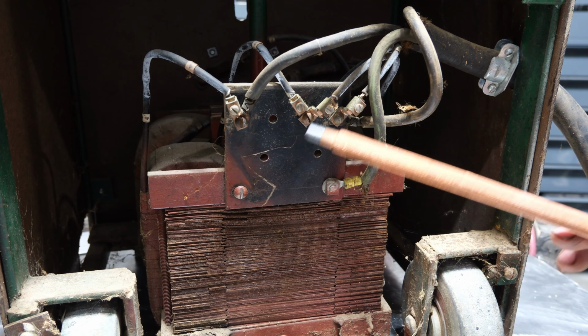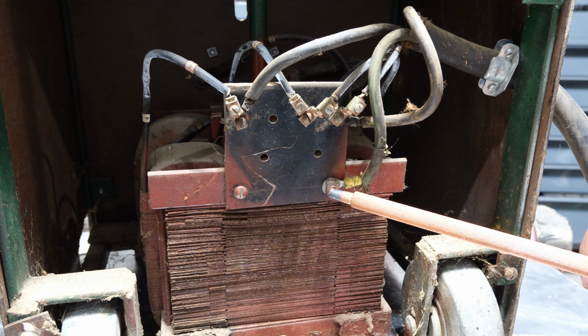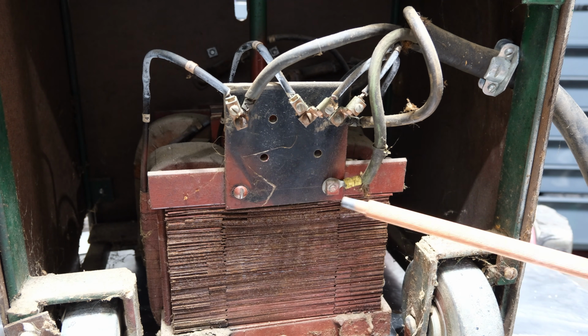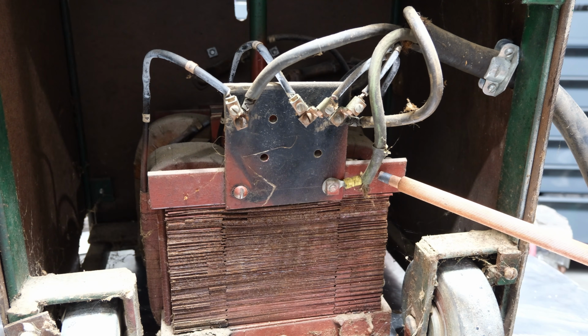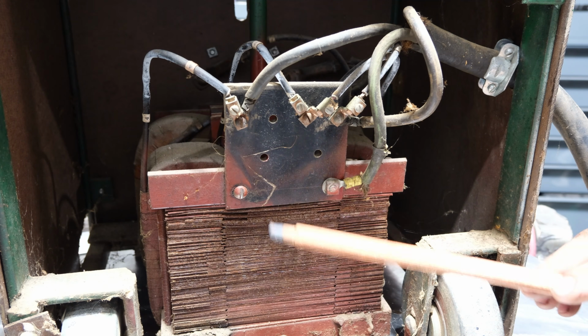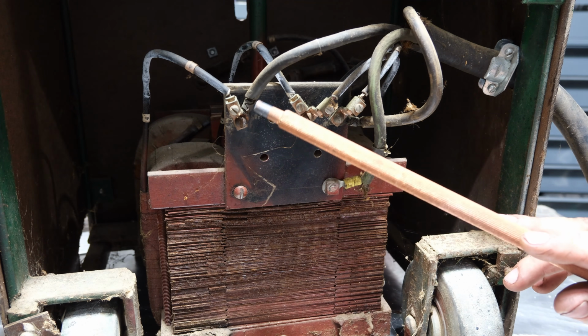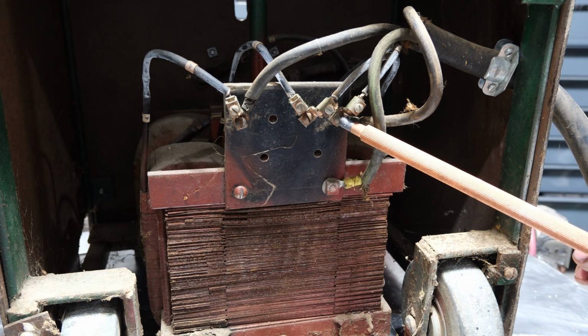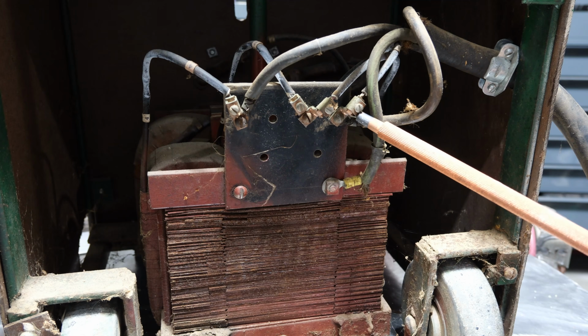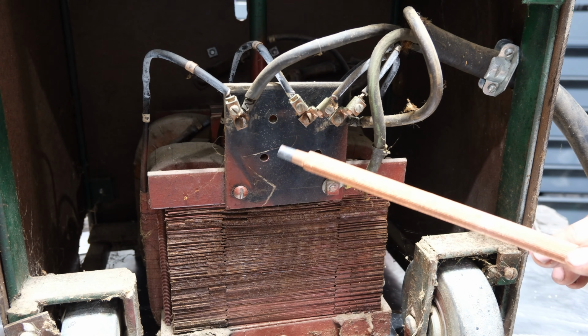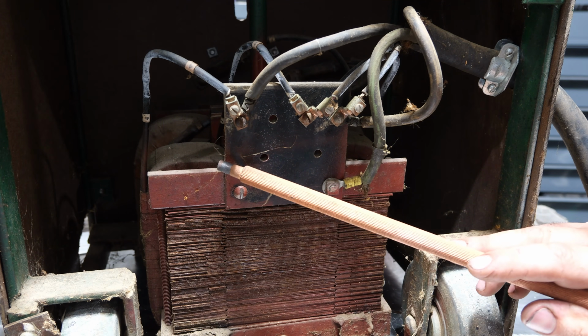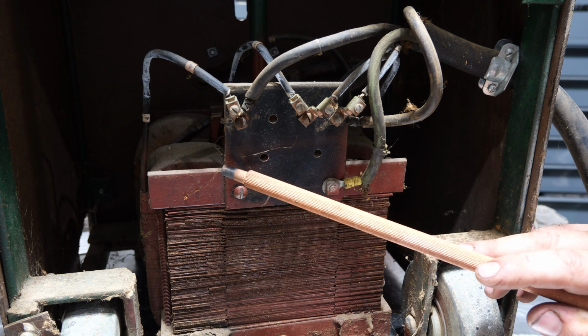So anyways, that power cord comes into this Bakelite or whatever plastic junction box, or junction plate, and they have the ground hooked to here, and it looks like they used their kids' erector set nuts to make this, and that more or less hooks up to the ground. Then the two hot leads from your 240 volt, one goes here, one goes here. Well, at least that's not loose, thought it was. And then that goes to the primary coil of the transformer.